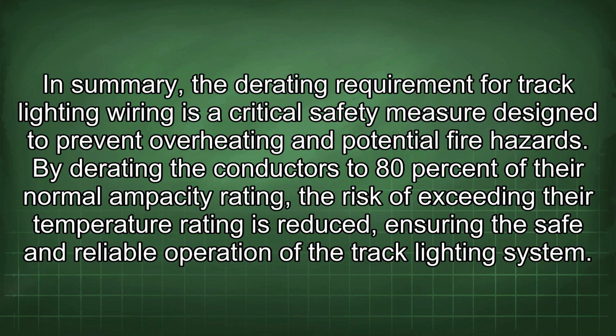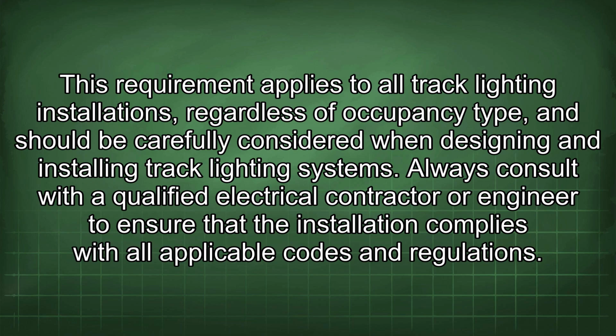By derating the conductors to 80% of their normal ampacity rating, the risk of exceeding their temperature rating is reduced, ensuring the safe and reliable operation of the track lighting system. This requirement applies to all track lighting installations, regardless of occupancy type, and should be carefully considered when designing and installing track lighting systems. Always consult with a qualified electrical contractor or engineer to ensure that the installation complies with all applicable codes and regulations.